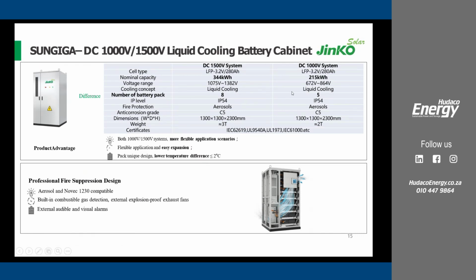So what determines whether to use 344 or 215 is ideally the voltage level. The voltage range for the 344, because of 8 packs, is more than 1,000 - up to 1,382. So you'd need a PCS which can accommodate this voltage range. What's mostly common, especially in the region, is less than 1,000, or rather the DC 1,000 volt systems - that's the 215 kilowatt hours, with a voltage range around 672 to 864.